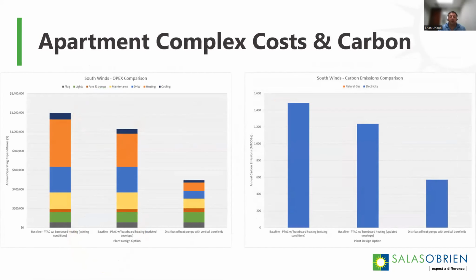When we look at OpEx and carbon, again we're really close to 50% total savings. Heating was very good because you're comparing electric resistance to a heat pump with a COP of 3.5 to 4, so that's 400% efficiency right there. Then you've got air conditioning savings as well, and domestic hot water savings. So there was a lot of energy and cost savings.